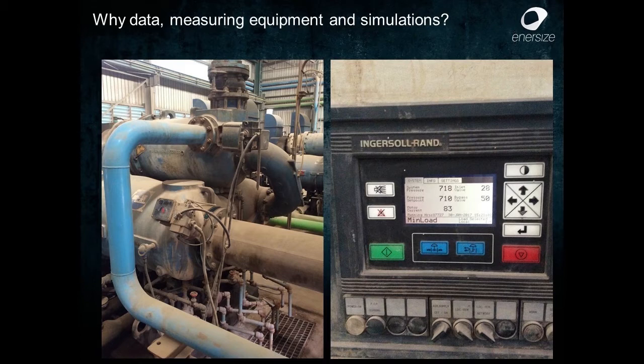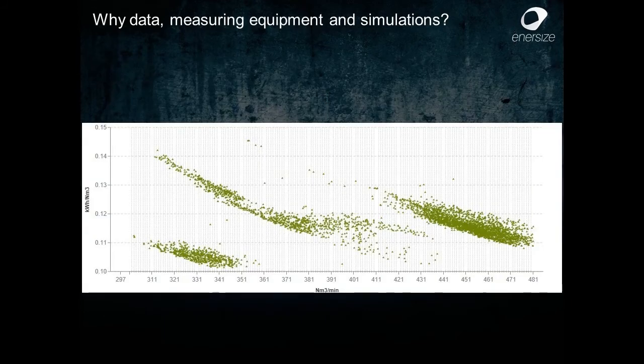Again, we have something similar in our simulations. Let's say you operate around 340 cubic meters per minute, and you can see the difference between these two clouds of data. And it could very well be that up here we operate a few compressors with the blow-off valve open, and here we have a better load sharing. This is important, and we need equipment and monitoring systems to see these things.